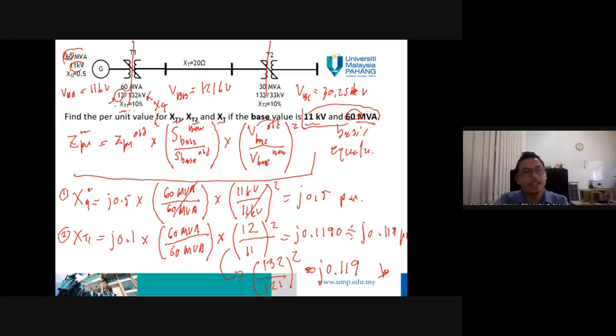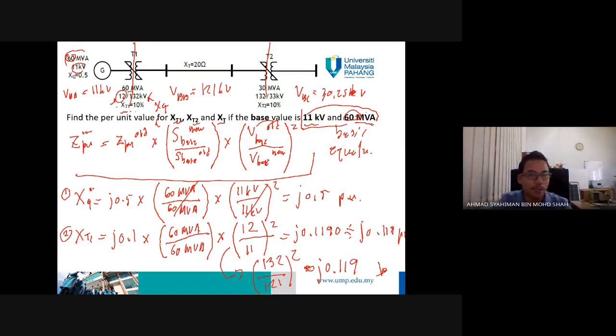This means that for the transformer case, you can take either primary or secondary, with the condition that the base voltage follows accordingly. If primary, then the base voltage for the primary is not 121 but 11 kV. Then, as I mentioned earlier, we divide the region in the middle of the transformer so we can differentiate it clearly — 12 over 11, or 132 over 121.